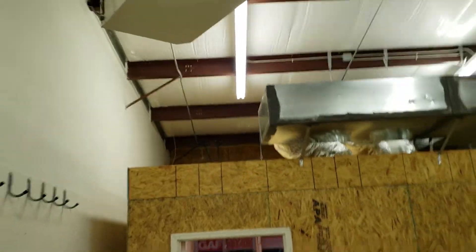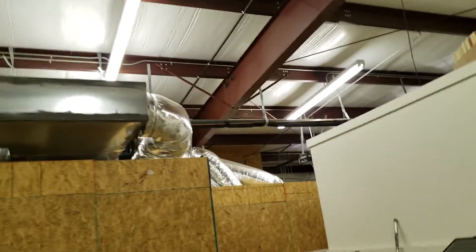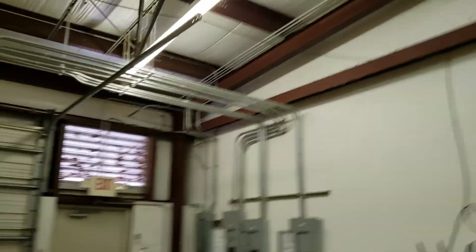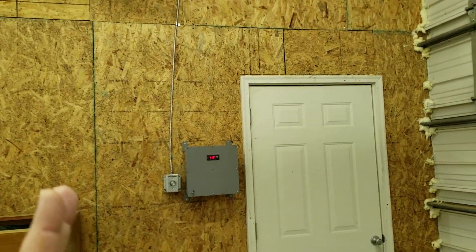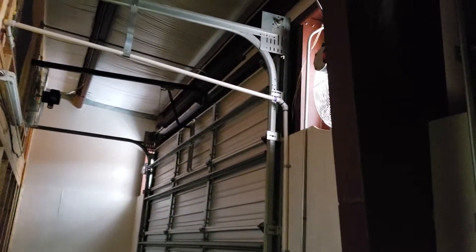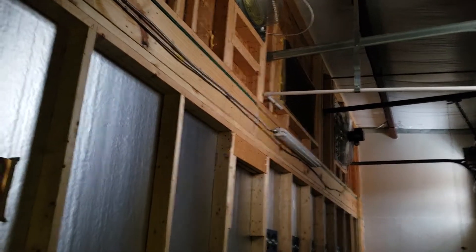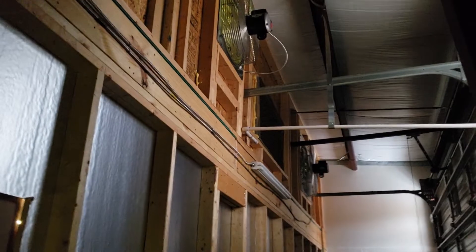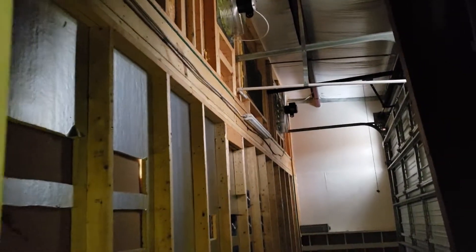In the winter time, we actually have extra fans up there at the top. We're going to take a walk around the back — there's probably another fan there to the right. What's happening here is we're reclaiming the heat from the facility. The hot air goes into this back tall wall where the door is and then it's expelled out the wall. Some of it is being cycled through that grill right there, which is being pulled in through the AC system. This is how we help balance the condition of the space. It's a variable speed motor and it can be adjusted to draw more or less based on what temperature we want the warehouse. We're already producing plenty of heat — it's just a matter of moving enough air.